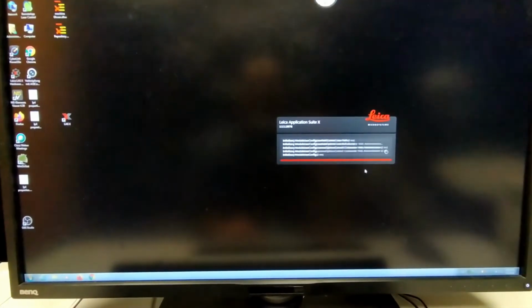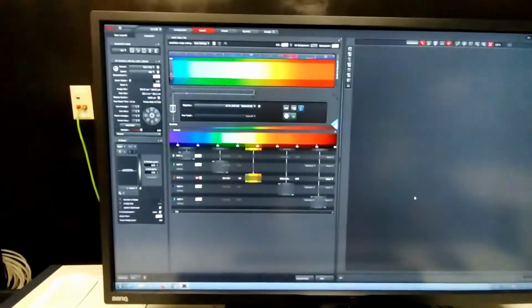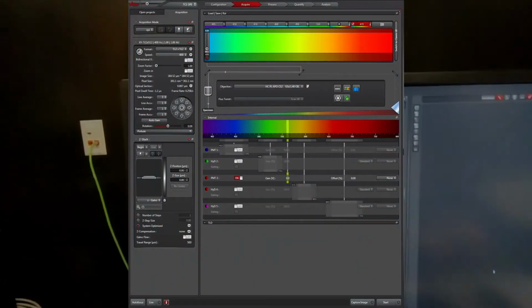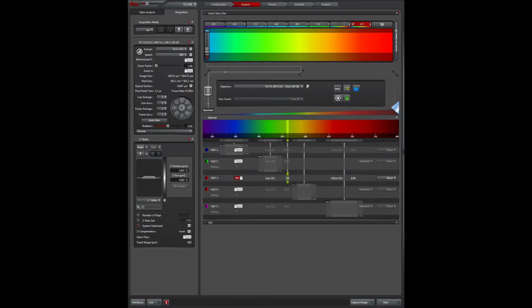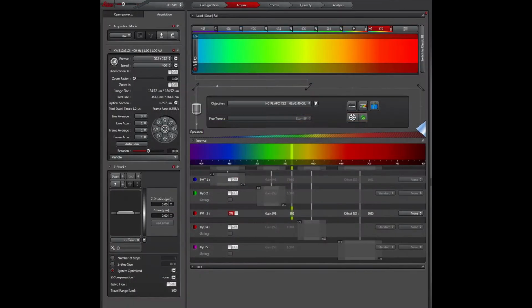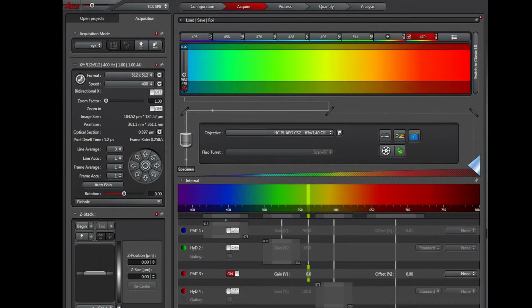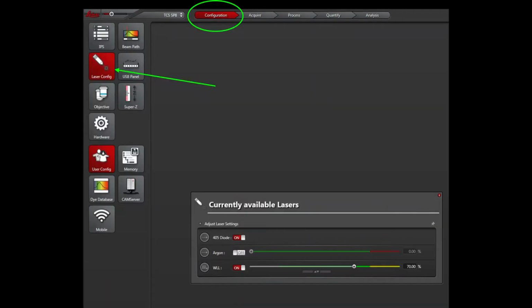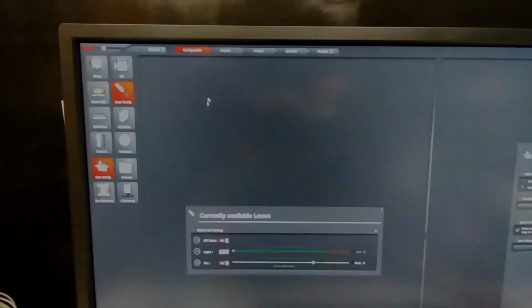When the software loads, the first thing we have to do is to turn on the lasers. And for that, click the configuration tab on top of the LASX software. And from there, click laser config button and turn on 405 and white light lasers only.